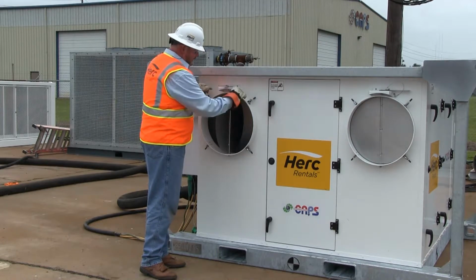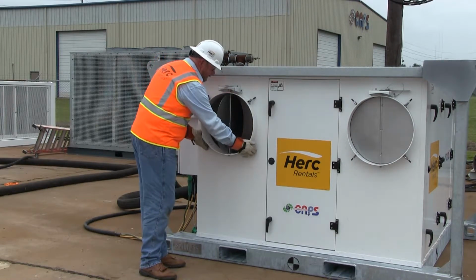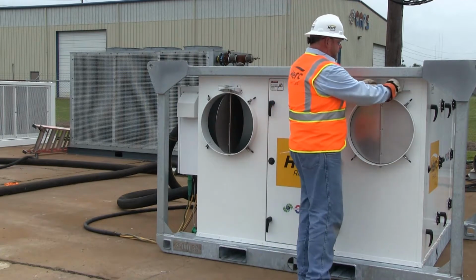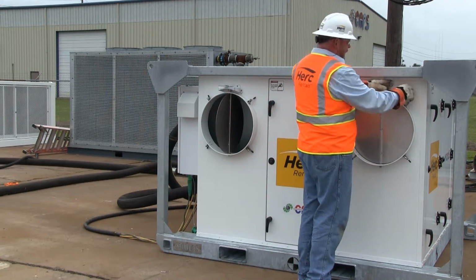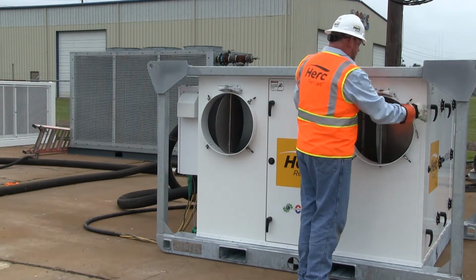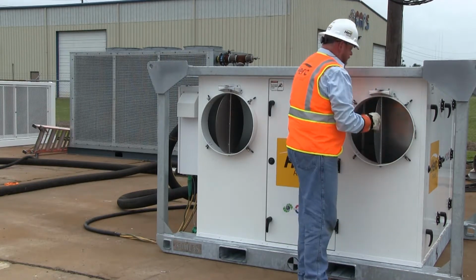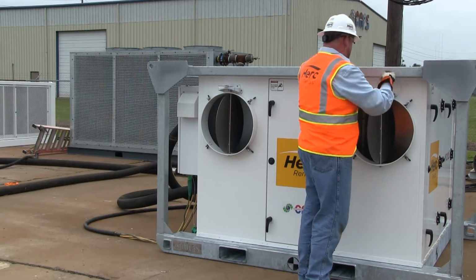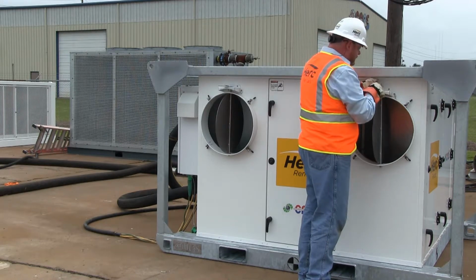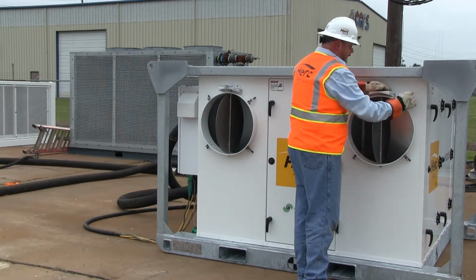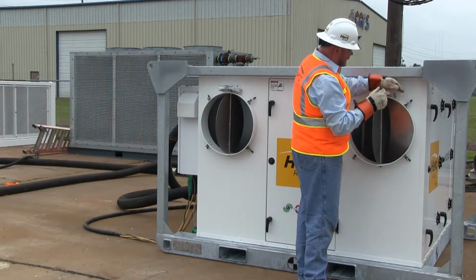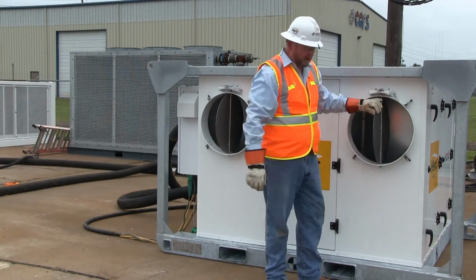We're going to open up the friction clamps on all 4 sides here. We're going to do that for both sides. The 50-ton air handler has got 2 outlets and 4 inlets. I have all those open there. We'll bring the pin back around and lock that. These quadrants here are for balancing air. If one duct on one particular area is longer than the other, use this for air balancing.